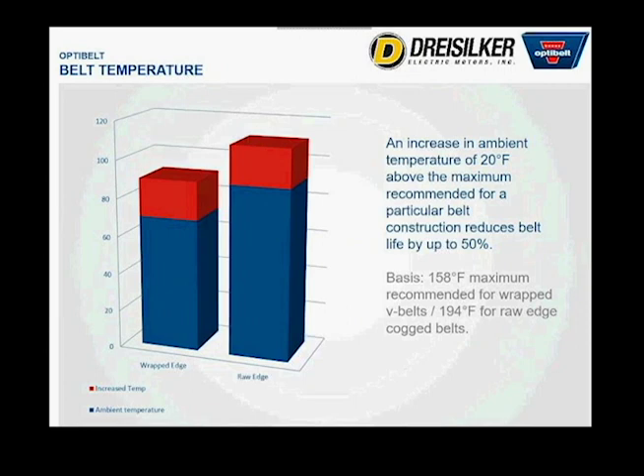Here's the effect that temperature has on the belt. An increase of 20 degrees Fahrenheit can reduce belt life up to 50%. So if you go over the maximum temperature of the belt, for every 20 degrees it's another half, and another half. It starts failing very quickly if you get an area that's way too hot.